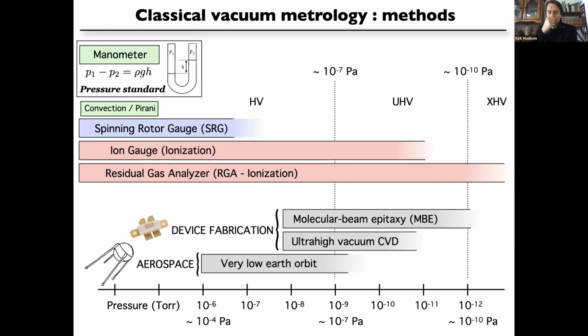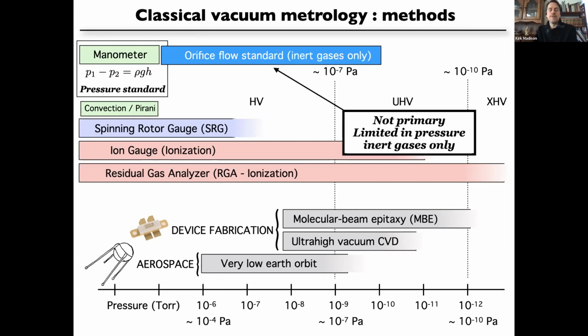Now, these ionization gauges require calibration, because the probability of ionization is not unity and the probability of detection is not unity. And so you have to calibrate them. The way they are calibrated today is by using an orifice flow standard. An orifice flow standard is basically a transfer standard that extends the range of a mercury manometer. The main limitations of the orifice flow standard are that it's not a primary standard, it's not standalone, it's a transfer standard. But more importantly, it is limited in the pressures that you can measure, and it is limited to inert gases only. So you can only calibrate an ion gauge for something like argon or helium or maybe nitrogen, but you can't calibrate an ion gauge for the gases present while it is used in molecular beam epitaxy.